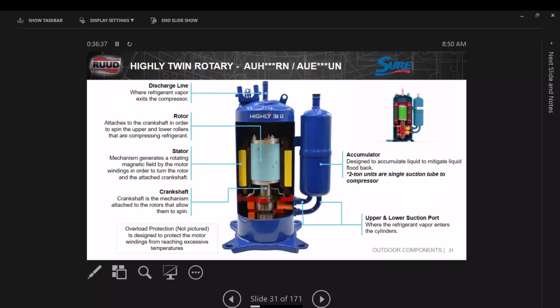Here's a cutaway of it. It's blue here, but it's going to be black. This is just a cutaway version. But as you can see, we got our discharge line there at the top. We have our rotor in the middle, the blue. Then we have our two stators on either side. And then our crankshaft. And then we get down here into the upper and lower suction port where it comes into the rotors down here.